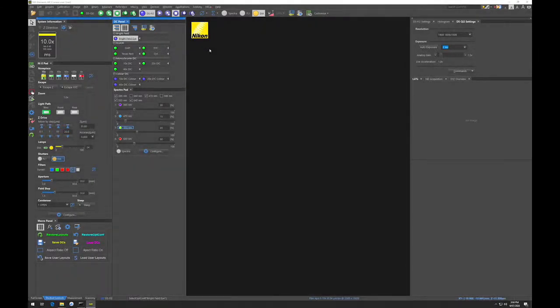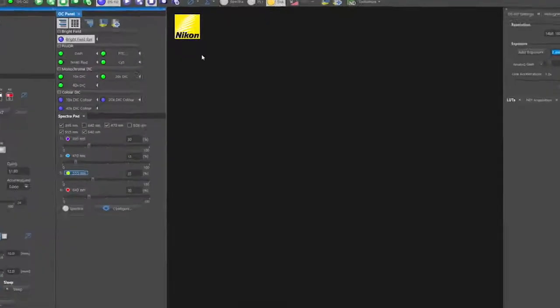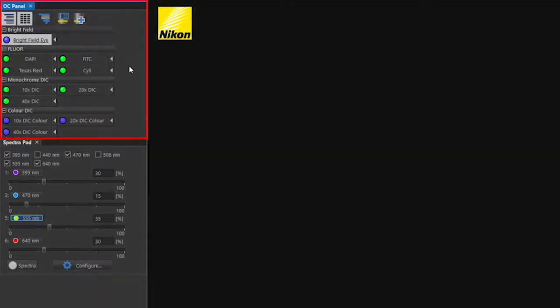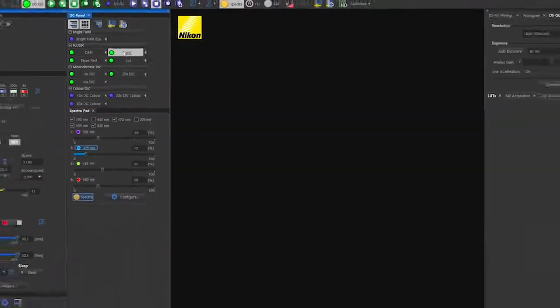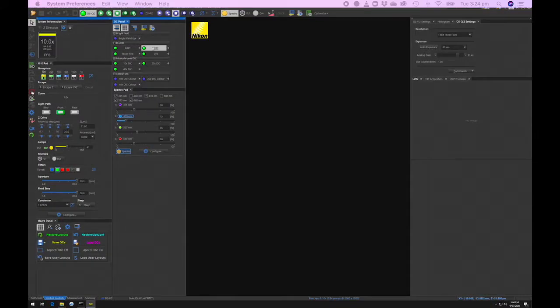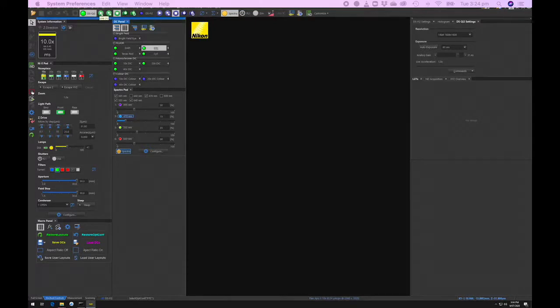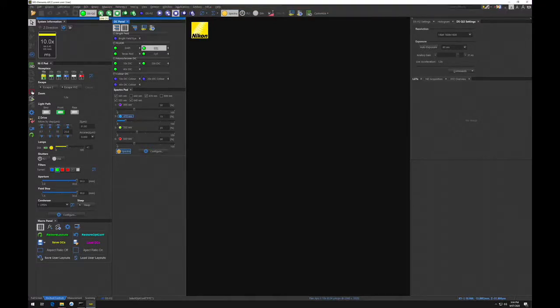If you are doing fluorescence imaging, select the relevant OC based on what fluorophores are in your sample. Here I have chosen the default FITC OC. This OC chooses the camera light path directed to the Qi2 monochrome camera. It also selects the 470nm LED for excitation and the FITC filter cube. Press play on the camera.